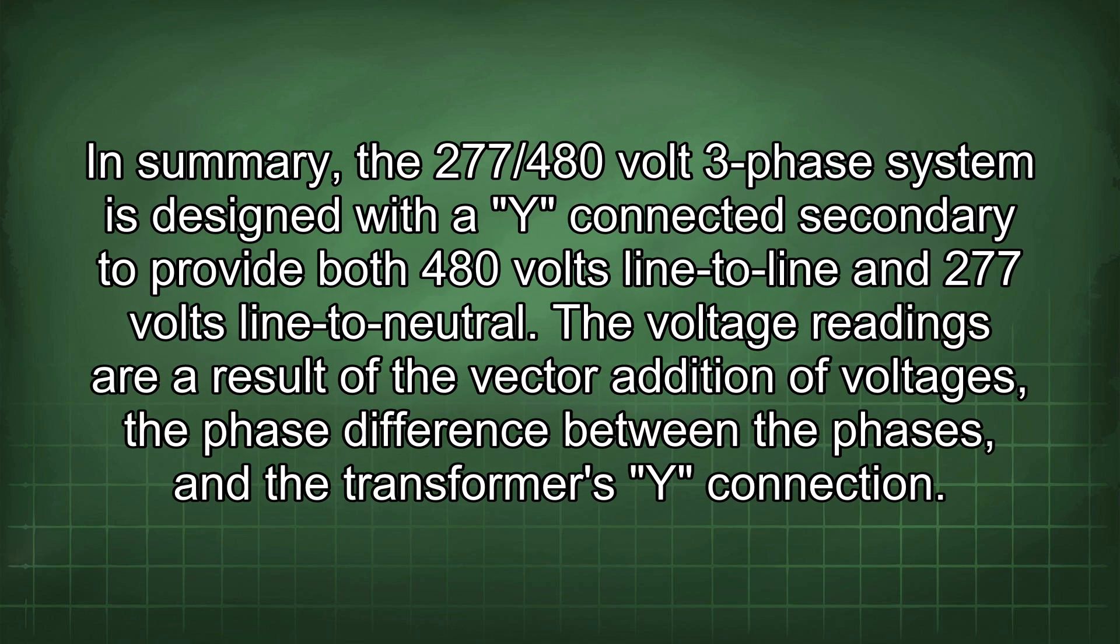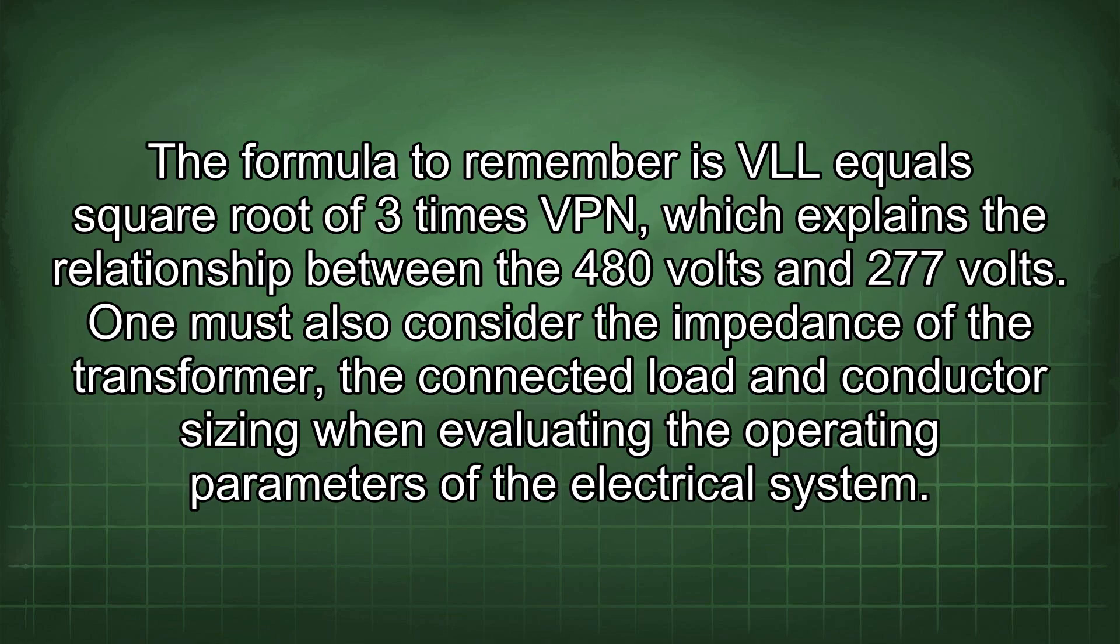In summary, the 277/480 volt 3-phase system is designed with a Y-connected secondary to provide both 480 volts line-to-line and 277 volts line-to-neutral. The voltage readings are a result of the vector addition of voltages, the phase difference between the phases, and the transformer's Y connection. The formula to remember is VLL = √3 × VPN, which explains the relationship between the 480 volts and 277 volts.